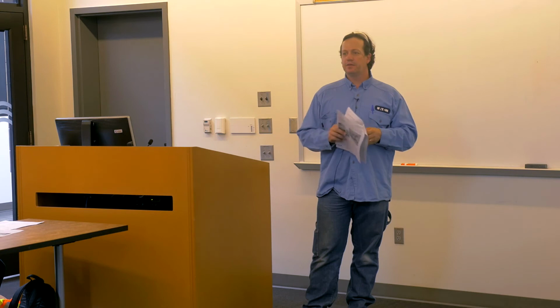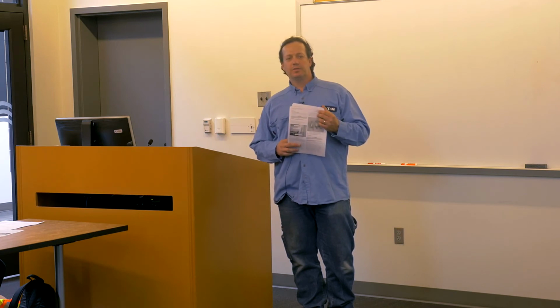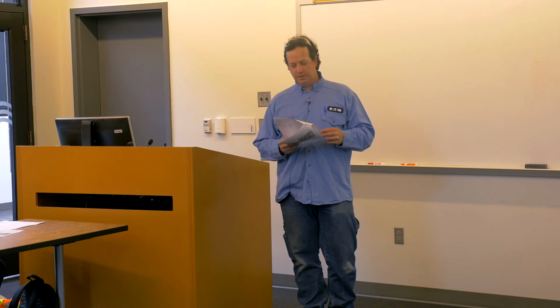Do you have copies of those? They're just the NETA - there's NETA acceptance testing, and also NETA maintenance testing. They're basically the same document, but some of the NETA tests are considered destructive testing. So for maintenance, especially on cable that's been in service, it's recommended now to just do your VLF, very low frequency testing, instead of the old way of doing DC high pots, because that's actually considered destructive testing.